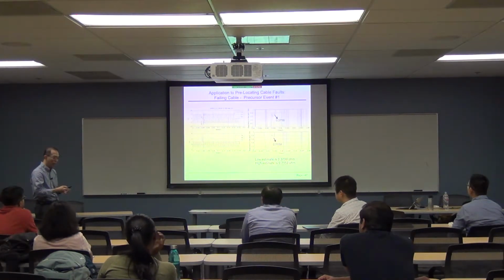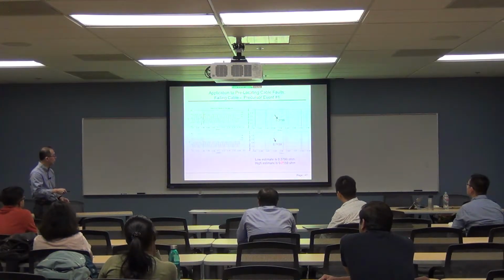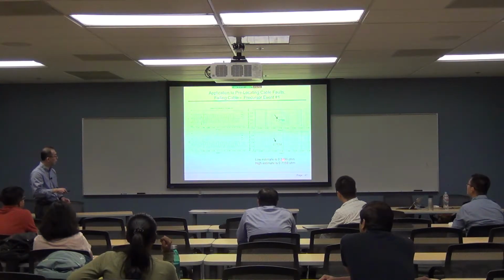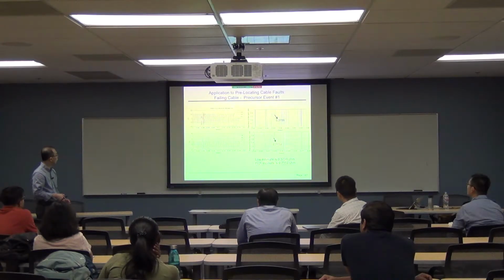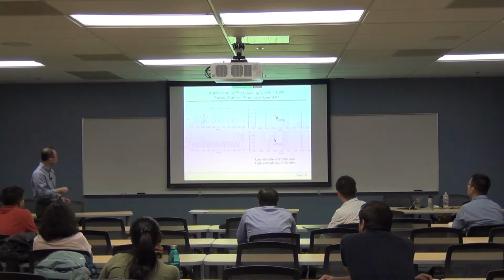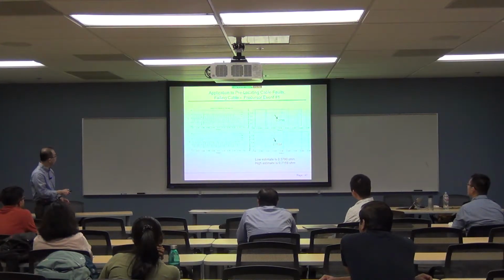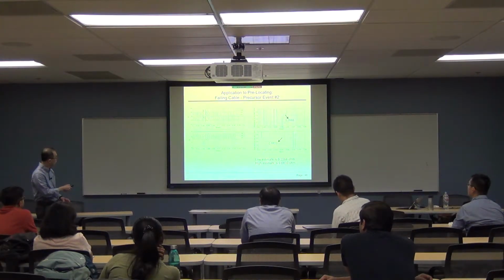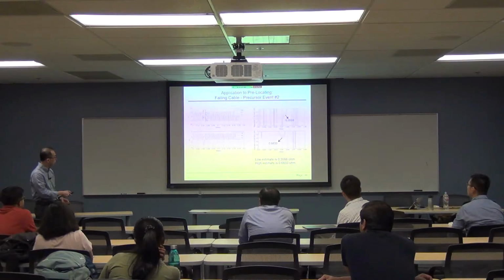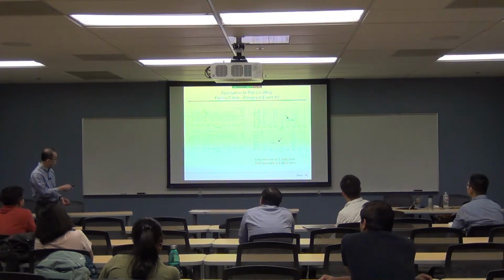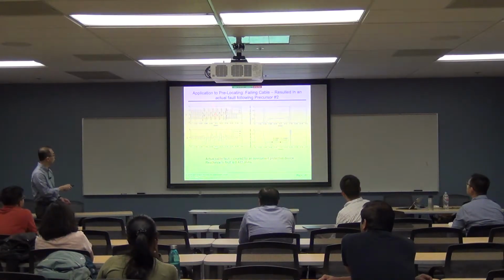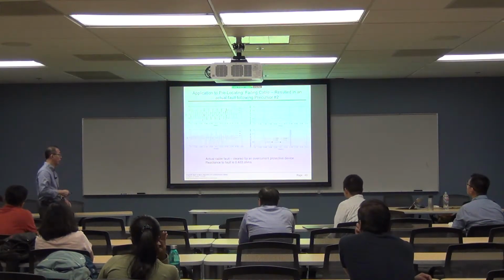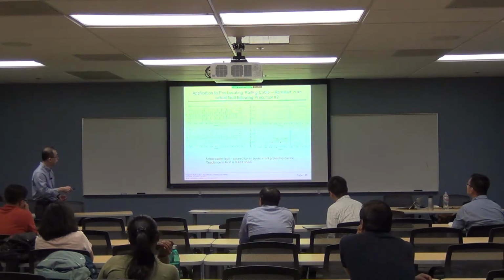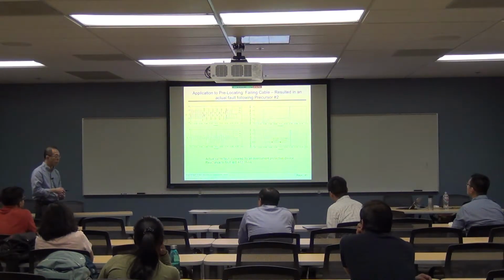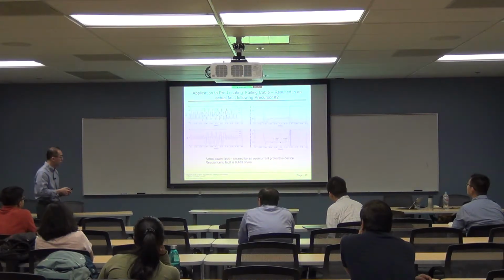Using the arc voltage and the impedance that you estimated, you can get an estimate that it is actually 0.38 ohms to 0.72 ohms. These are the incipient faults happening here, and then a few cycles later we estimate it. You can see the numbers: this is 0.38 to 0.7, this is also 0.35 to 0.7 approximately, and this is when the full-blown fault happens. When the full-blown fault happens, it's not difficult to estimate the fault location. We estimated it's about 0.48 ohms, which is very well within those initial estimates.